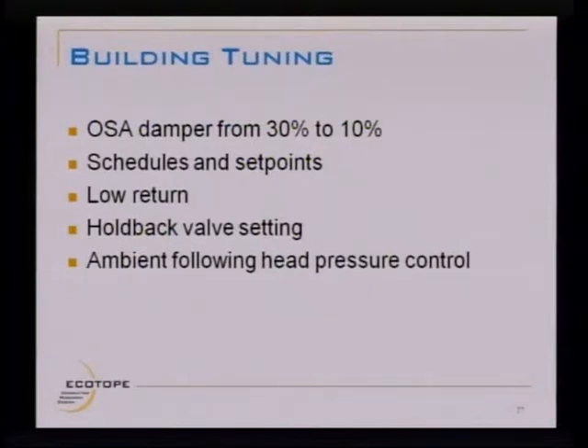So we went through a commissioning process and got the store more or less functioning the way that the designers intended. And that's really what commissioning is supposed to do. It's to make sure that the building is set up based on the way that the design had intended it. But once you go through that, it still doesn't necessarily mean that the building is functioning the best that it could be.